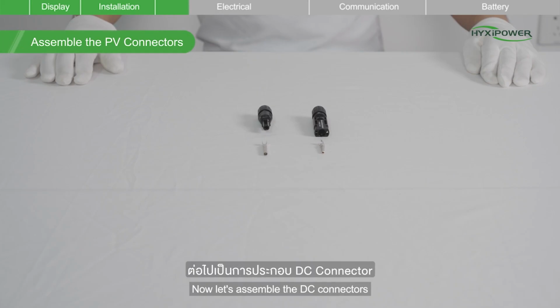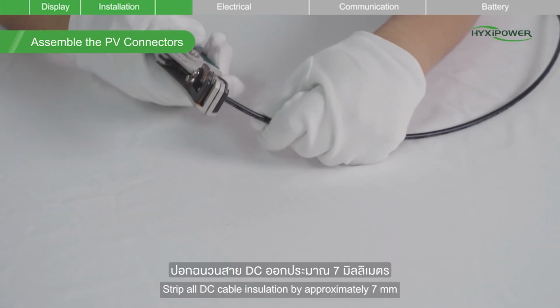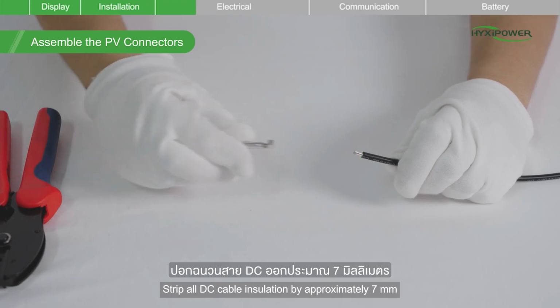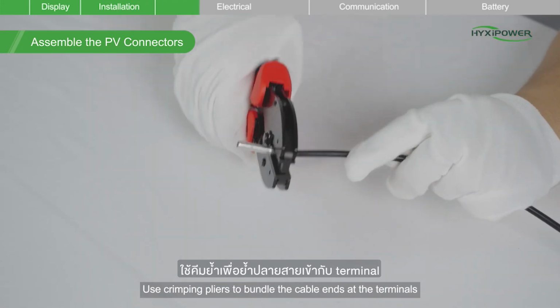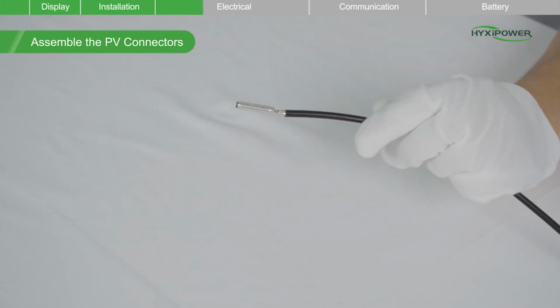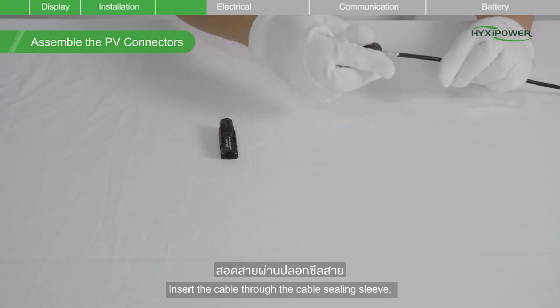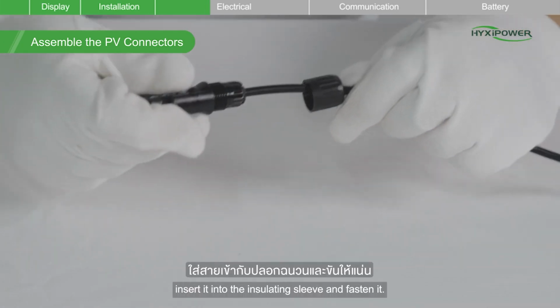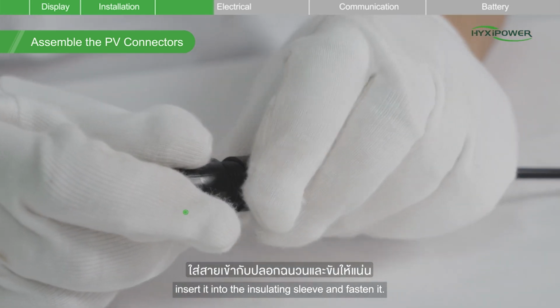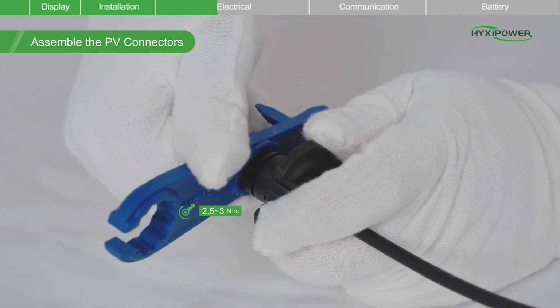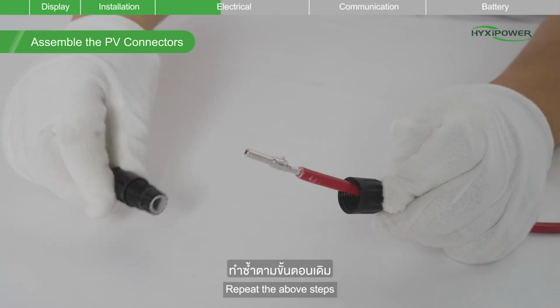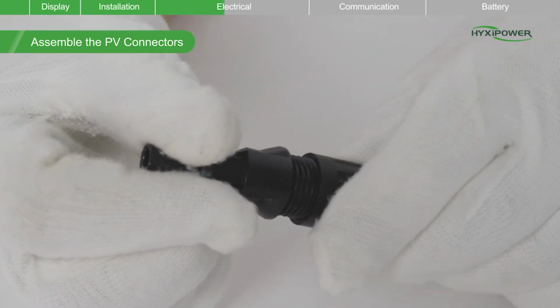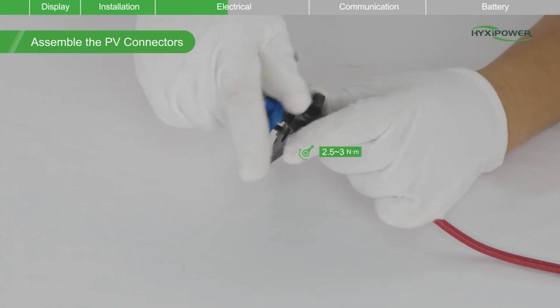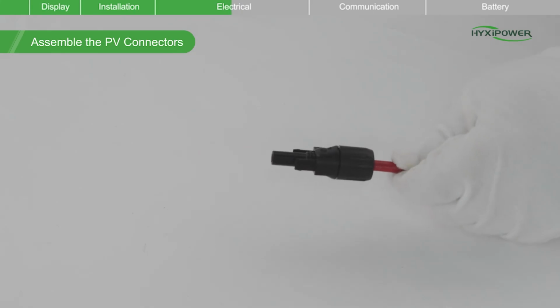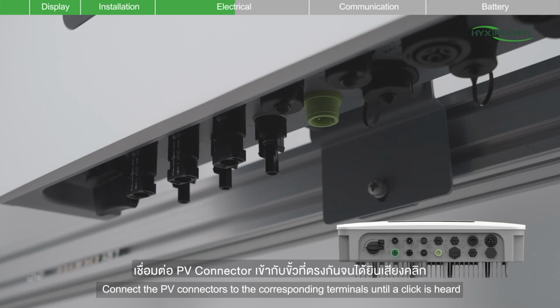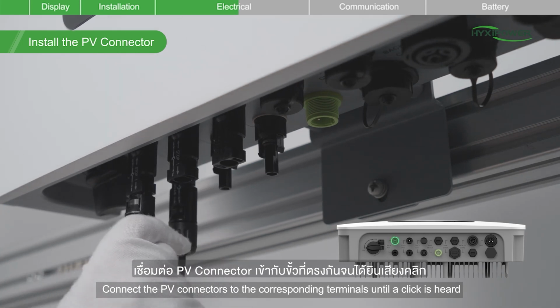Now, let's assemble the DC connectors. Strip all DC cable insulation by approximately 7 mm. Use crimping pliers to bundle the cable ends at the terminals. Insert the cable through the cable sealing sleeve. Insert it into the insulating sleeve and fasten it. Repeat the above steps. Connect the PV connectors to the corresponding terminals until a click is heard.